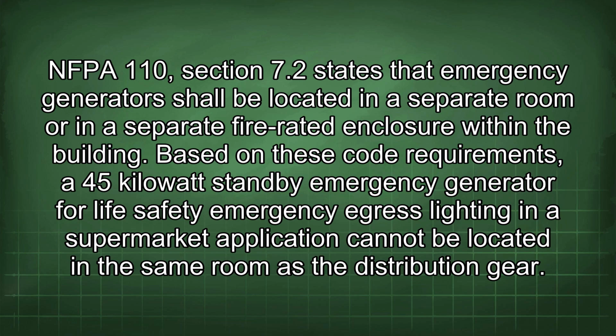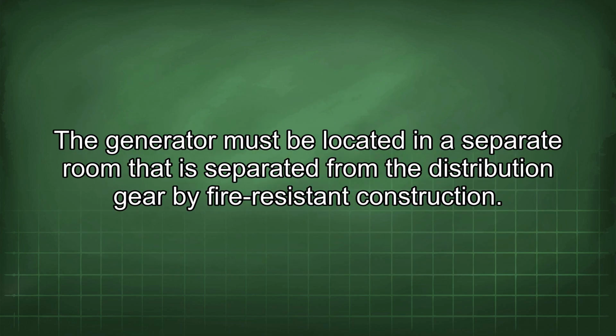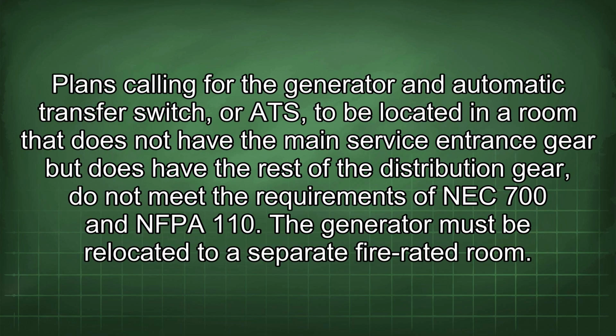lighting in the supermarket application cannot be located in the same room as the distribution gear. The generator must be located in a separate room that is separated from the distribution gear by fire-resistant construction. Plans calling for the generator and automatic transfer switch, or ATS, to be located in a room that does not have the main service entrance gear but does have the rest of the distribution gear, do not meet the requirements of NEC 700 and NFPA 110. The generator must be relocated to a separate fire-rated room.